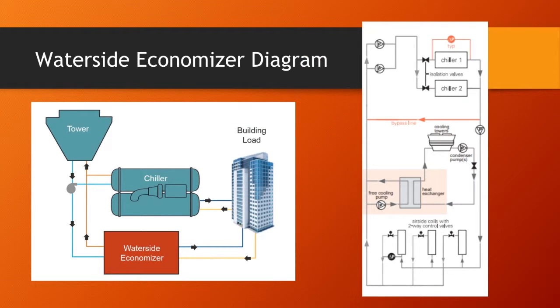This setup's a little more common only because you can simultaneously run chiller plant and the water side economizer, which can also help save energy because you're not running the chiller at full capacity. You might be able to get away with running the chiller at 50% capacity versus 100%.